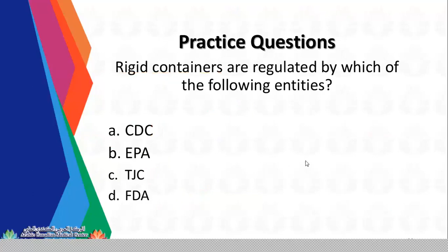Containers are required to have a 510K certification that they will perform as effective packaging materials. So even in CSSD, especially if you are dealing with chemical indicator pouches, it is controlled under FDA. Okay, even your biological.